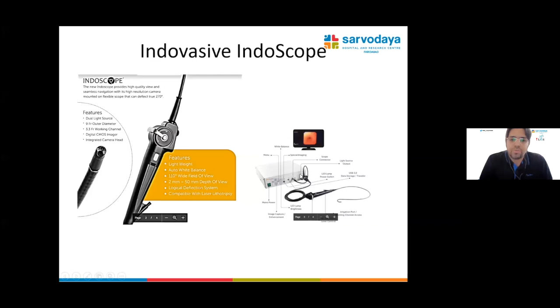So one scope I am pretty much excited about is the Indovasive IndoScope. It comes with a dual light source. You can see here in the tip that there are two illuminating bundles. It has a 9 French outer diameter and a 3.3 French working channel. It has a CMOS image sensor and an integrated camera head. And this is the processor. So basically, you don't need a separate screen for this. You can use the processor and attach it to your usual monitor in the OT.